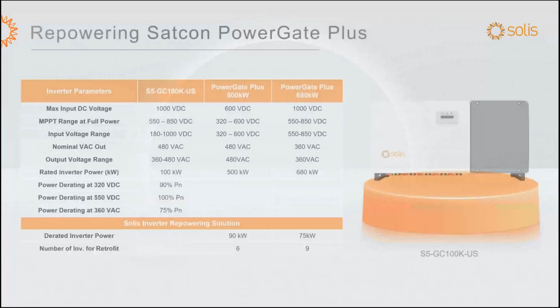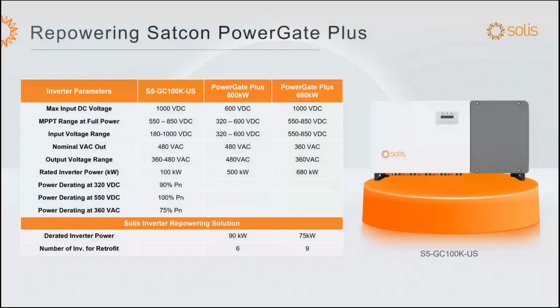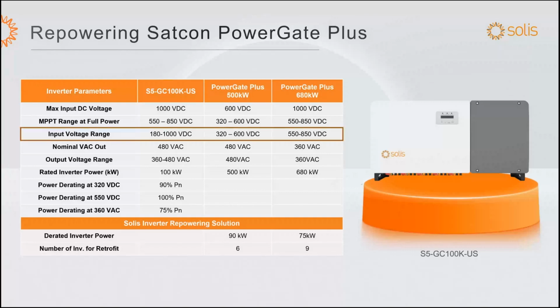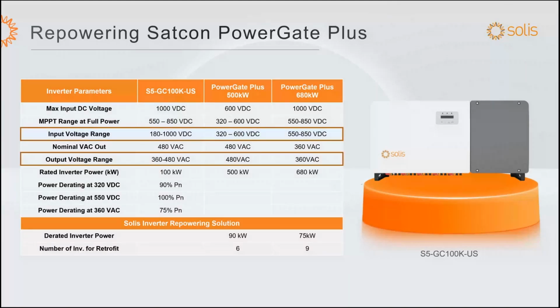This is the specification of the Satcon PowerGate 500 and PowerGate 680, compared with our S5 100 kilowatt string inverter. Those are the comparison of the specifications. The first thing we'll review is input voltage range. Can we cover the input voltage range of the Satcon inverter? Based on this, the 100 kilowatt inverter can cover the input voltage range without any issues. The next thing we'll review is the output voltage range. Here too, we can cover the output voltage range of the Satcon inverter.